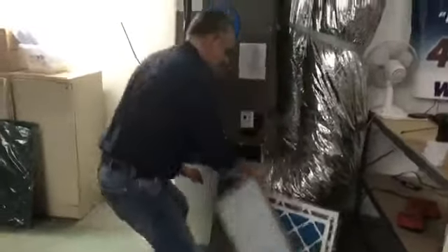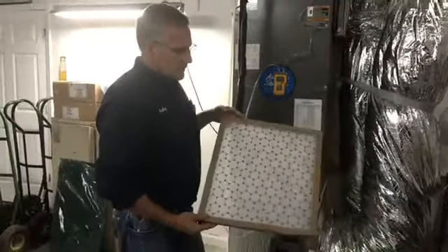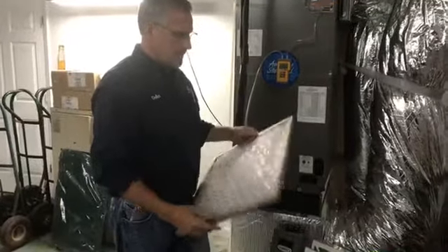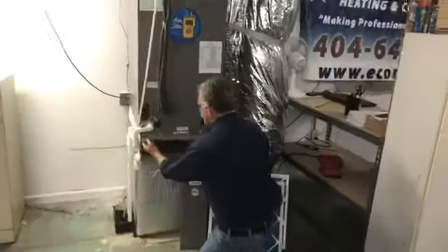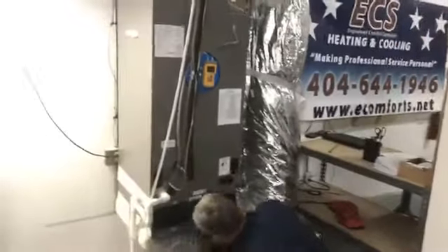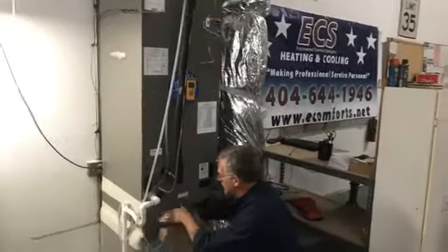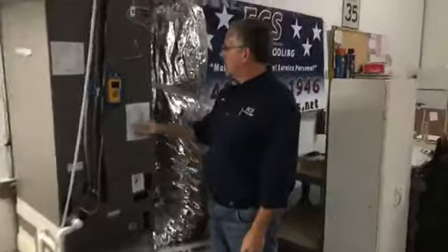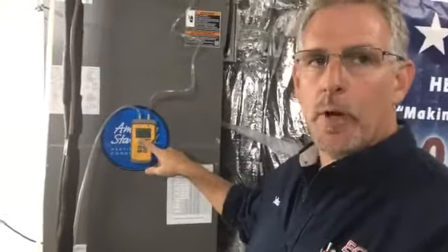So let's put in the El Cheapo filters, okay? This is the filter that the technician told the homeowner that he recommends. So, come over here, put this in. Should be covered. All right, that was a MERV 4 we just put in there. That puts us at a 0.6. Remember, we want a 0.5.